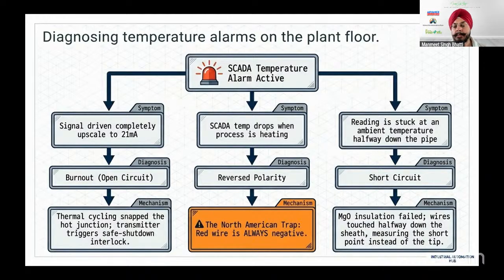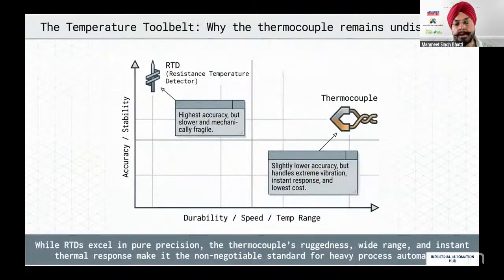Next is the reading is stuck at an ambient temperature halfway down the pipe. What it means is it can be a short circuit. Some temperature or millivolt is coming, but the MI insulation has failed, so it has gone down. Wires have touched halfway, so it is not touching the tip. The temperature is not coming from the tip, but from somewhere in between. So it's holding over there, not going up or down. These are the 3 major types of problems with thermocouples that we have already faced.